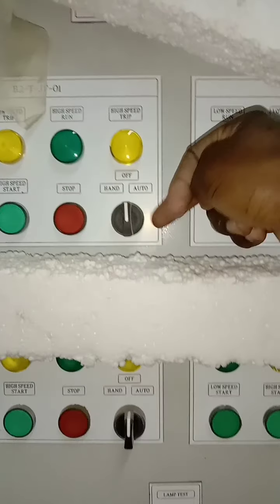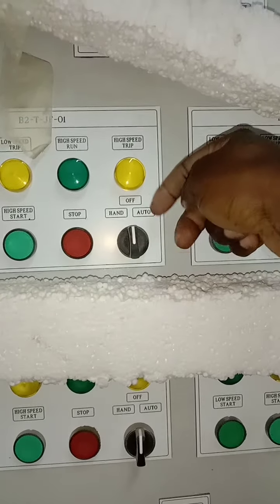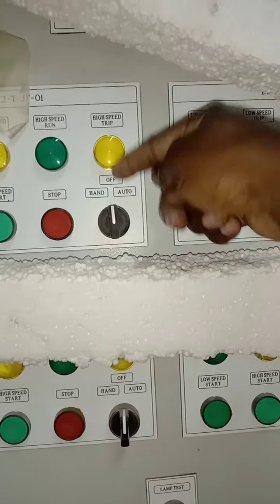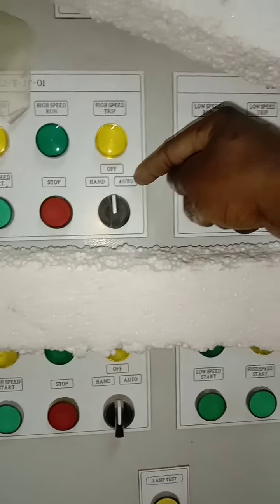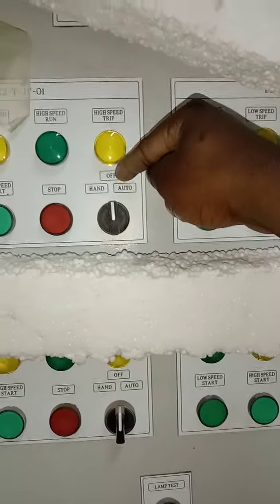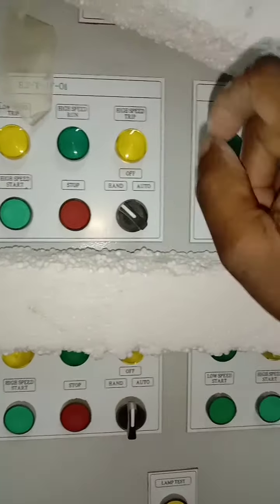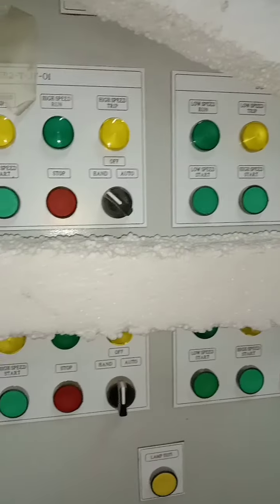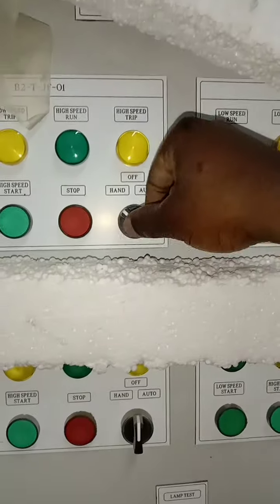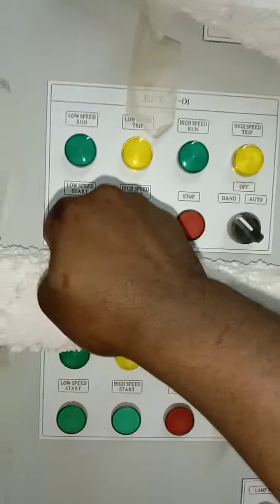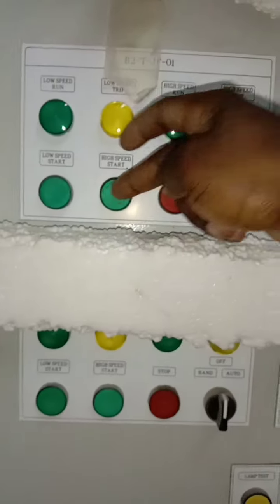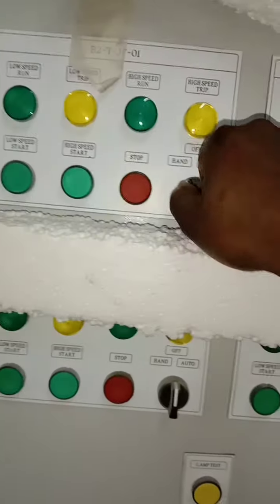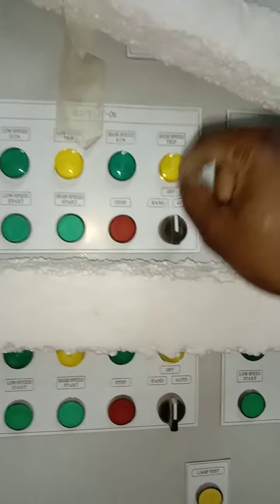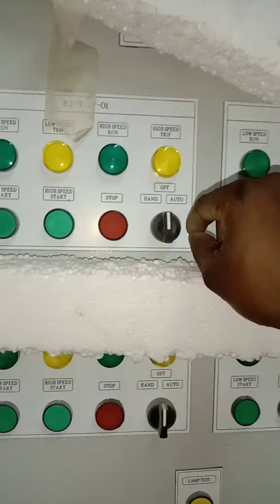And then on this other side you see a selector switch which has hand, off, and auto. So hand is for manual, auto is automatic, and off is putting off the fan. If I turn it to hand, it means I have to operate the jet fan in manual condition. Therefore I have to press the start button in order to put on the fan either at low speed or at high speed. And if I turn it to off, the fan will be shut off. There is no power given to the fans.